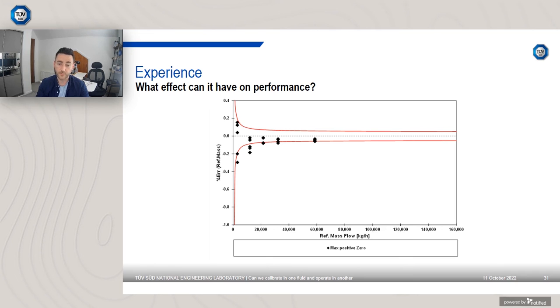So that means the zero can either be positive or it can be negative in any operation, because you have your inlet pickoff and outlet pickoff. If the inlet pickoff is greater than the outlet pickoff, you'll have a positive zero. If the inlet pickoff is less than the outlet pickoff, you'll have a negative zero. Now we have our max permissible zero, and I've set it to the positive version for this, and you can see the results again. They're not great.